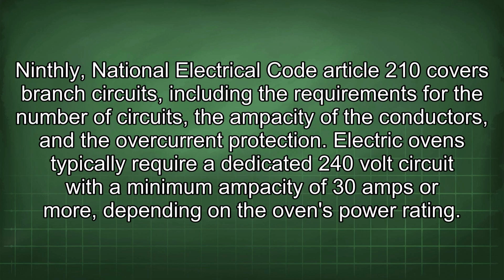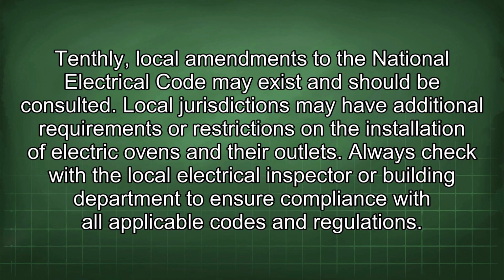Ninthly, National Electrical Code Article 210 covers branch circuits, including the requirements for the number of circuits, the ampacity of the conductors, and the overcurrent protection. Electric ovens typically require a dedicated 240-volt circuit with a minimum ampacity of 30 amps or more, depending on the oven's power rating. Tenthly, local amendments to the National Electrical Code may exist and should be consulted. Local jurisdictions may have additional requirements or restrictions on the installation of electric ovens and their outlets. Always check with the local electrical inspector or building department to ensure compliance with all applicable codes and regulations.